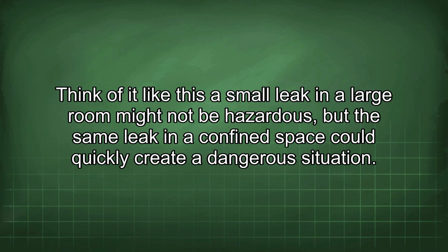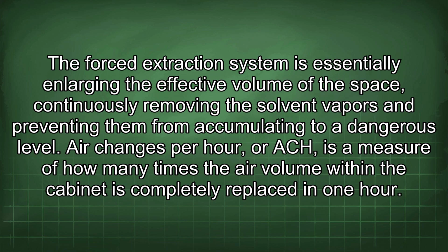Think of it like this: a small leak in a large room might not be hazardous, but the same leak in a confined space could quickly create a dangerous situation. The forced extraction system is essentially enlarging the effective volume of the space, continuously removing the solvent vapors and preventing them from accumulating to a dangerous level. Air changes per hour, or ACH, is a measure of how many times the air volume within the cabinet is completely replaced in 1 hour.